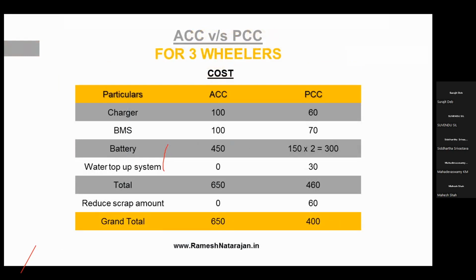Now I come to the cost. The charger of a lithium ion is definitely costlier than a charger of a lead acid battery. So if the charger is say 100 units, here it's 60 units. Now, if the battery management system is say 100 units, because we don't have the temperature sensors and all these, we can easily give a battery management system at say 70 units, 70% of the cost of a lithium ion. Now, if the battery is costing 150, here, even if you give 2 batteries, considering the cost to be 3 times more than a lithium ion, you will have 150 into 2, 300. And an additional cost is the water topping up system, the autofill system, which is generally about 10% of the cost of the battery. So that's about 30.